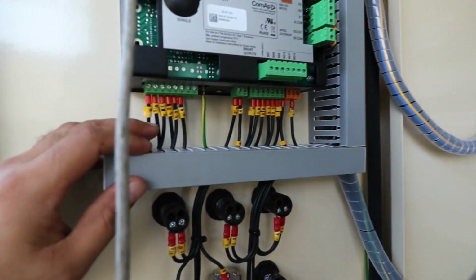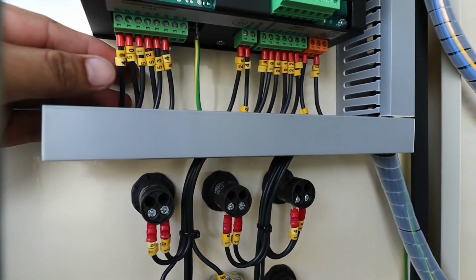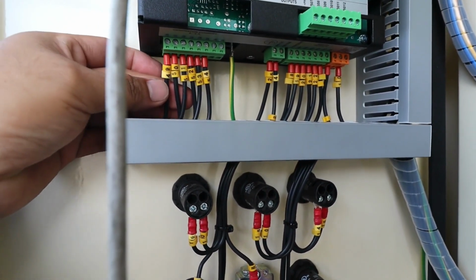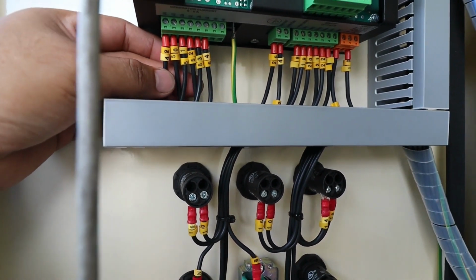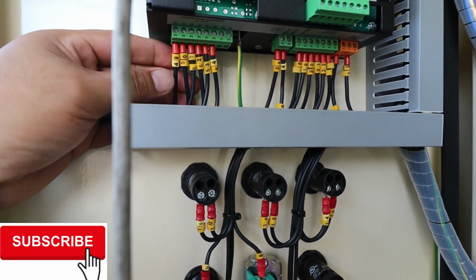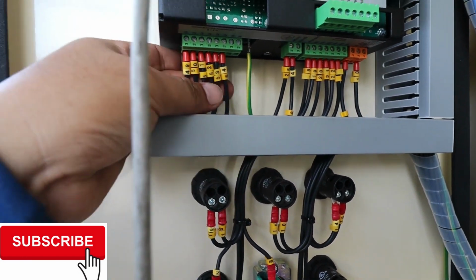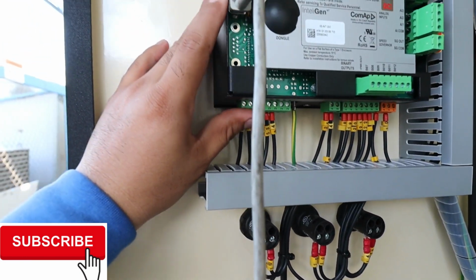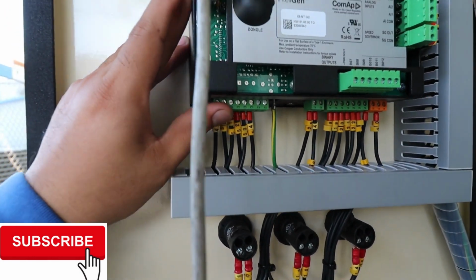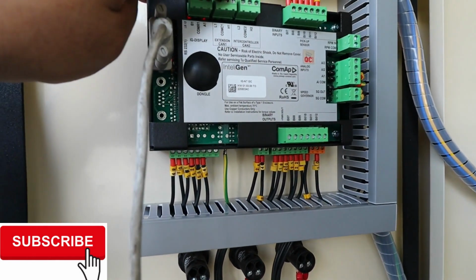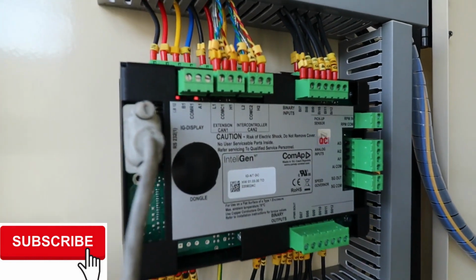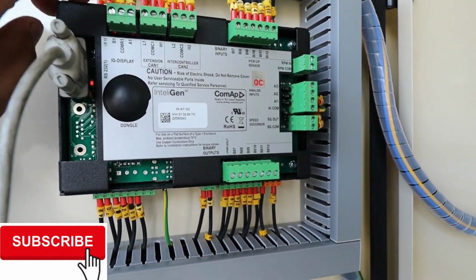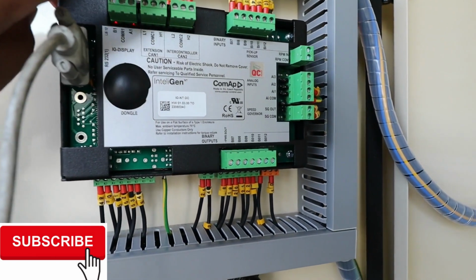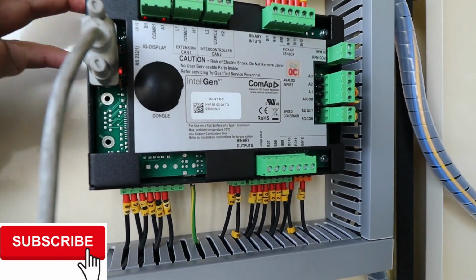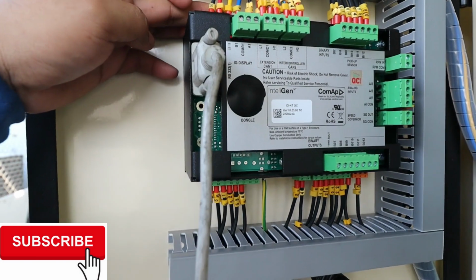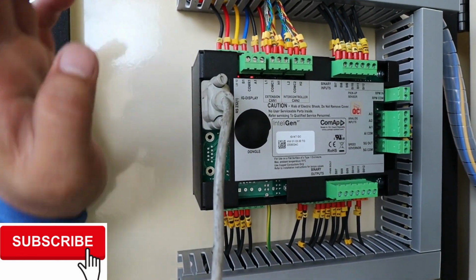So here is our generator CT. This is the connection here. We have the common, the line, the CT1, CT2, CT3. So that is common for you already. Here is our CAN for our ECM connections. This is only for your ECM2. For example, this is your extra. And here is our voltage sensing from your generator side and for your incomers.